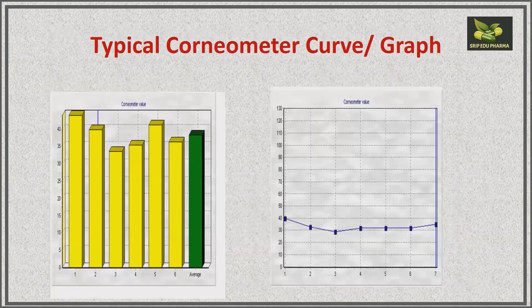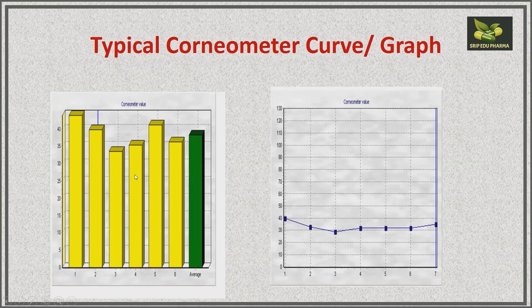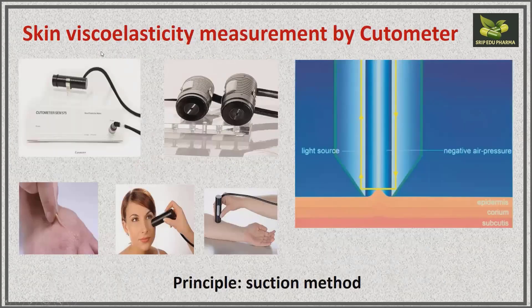This is the typical corneometer curve obtained when taking readings. Values are taken in arbitrary units and at the end an average value is obtained. Both a graph and a curve are obtained from the instrument, and an Excel sheet with all readings is also generated. Initially, plain skin readings are taken without applying any formulation, and then readings are taken after applying the formulation. The cutometer for skin viscoelasticity is shown — both single and dual types are available.